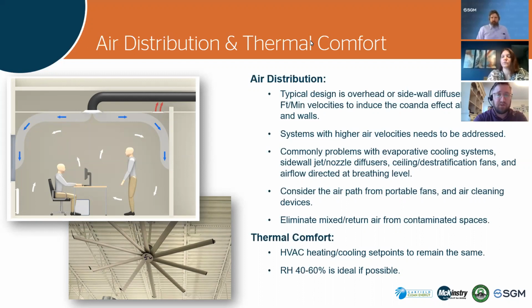The data shows so far in the early studies that this mixed return air is getting caught in filters and is not a big concern. Additionally, one note on thermal comfort, you're going to keep your set points in the building the same. And if you have the ability to adjust relative humidity, target 40 to 60%.